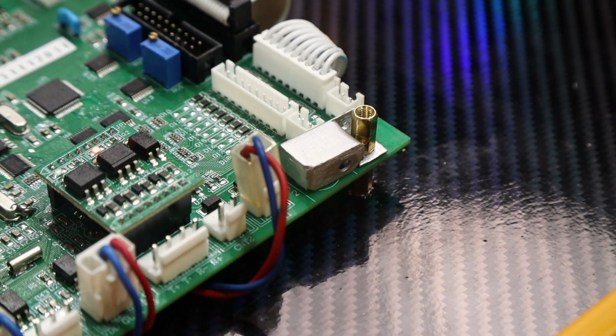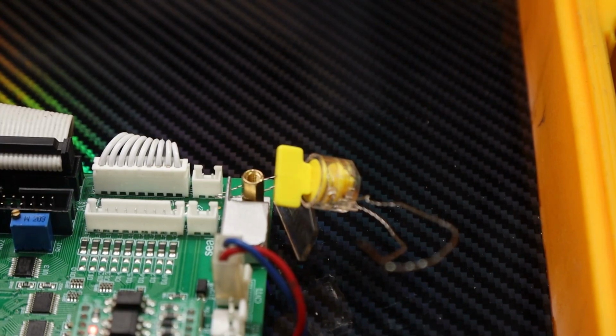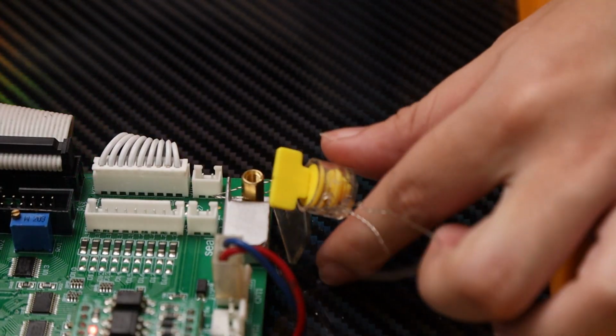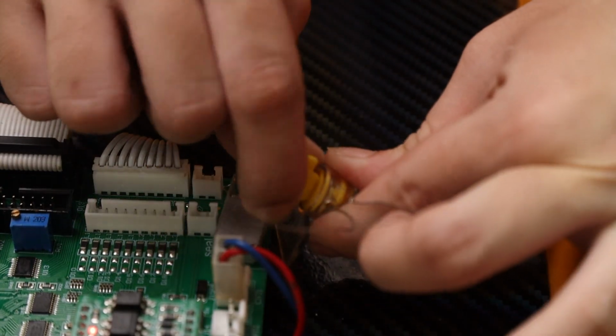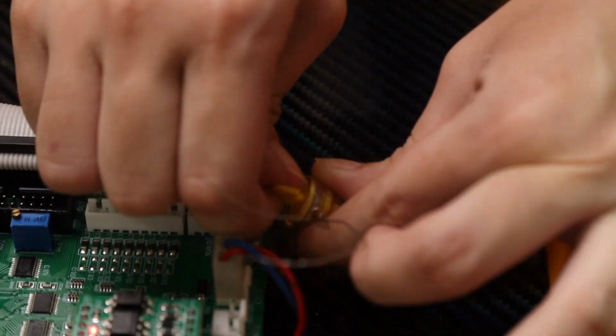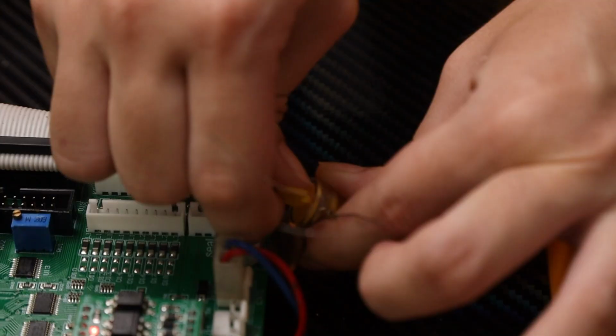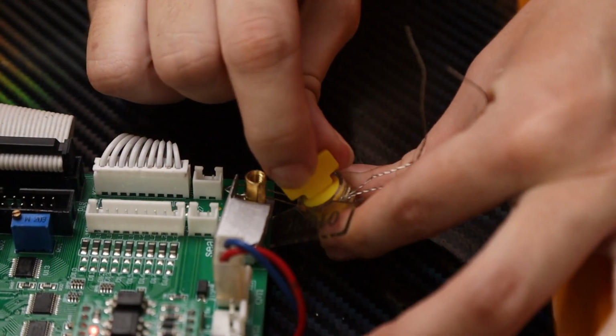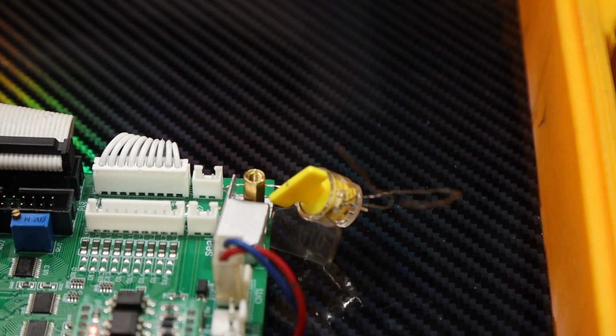Replace the seal cover. Securely tighten the seal cover screw or knob to lock in the setting. Reseal the calibration mechanism. Use the seal wire to reseal the calibration mechanism, preventing unauthorized tampering, as required by regulations. Record the calibration results. Enter the calibration results, including the final adjustments and test results, into the maintenance log for future reference. Report as required.